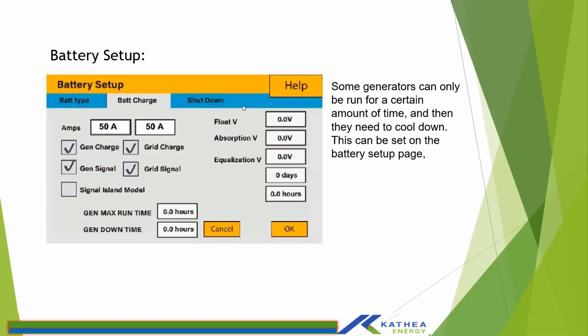So you need to set also the charging current that you should use when using the generator to charge your batteries. Because if you are using the generator and your load is high and your batteries are charging at the same time, that could impact your generator. Because if the total power that is used to charge the battery and supply the loads exceeds the generator, that could actually choke your generator.